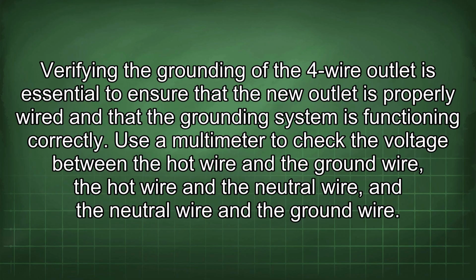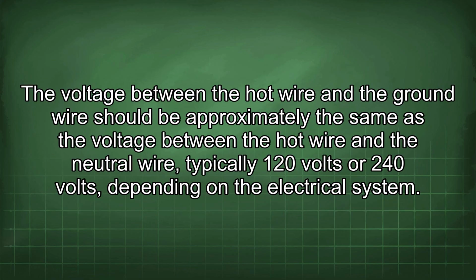Verifying the grounding of the 4-wire outlet is essential to ensure that the new outlet is properly wired and that the grounding system is functioning correctly. Use a multimeter to check the voltage between the hot wire and the ground wire, the hot wire and the neutral wire, and the neutral wire and the ground wire. The voltage between the hot wire and the ground wire should be approximately the same as the voltage between the hot wire and the neutral wire, typically 120 volts or 240 volts, depending on the electrical system.